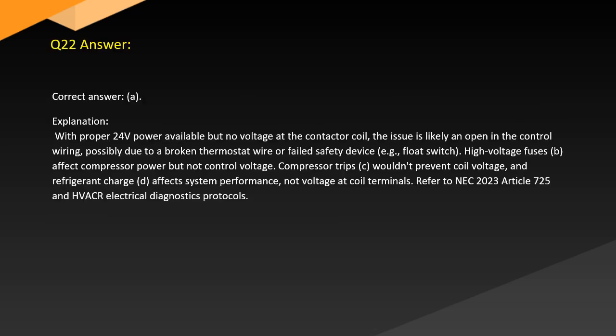Answer. Correct answer A. Explanation. With proper 24 volt power available but no voltage at the contactor coil, the issue is likely an open in the control wiring, possibly due to a broken thermostat wire or failed safety device, e.g. float switch. B. High voltage fuses affect compressor power but not control voltage. C. Compressor trips wouldn't prevent coil voltage. D. Refrigerant charge affects system performance, not voltage at the coil terminals. Refer to NEC 2023 Article 725 and HVACR Electrical Diagnostics Protocols.